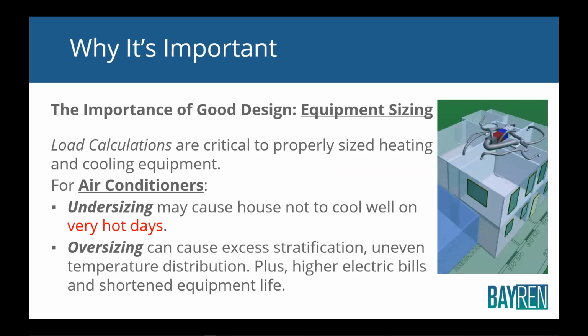The windows have more to do with the load of a house, and the direction they're facing, than the square footage of a house. So to size an air conditioner based on the square footage of the house is actually kind of dumb. I would be much more respectful of a contractor who says, I do so many tons per square foot of glass, or I look at west facing glass, that's how I size air conditioners. I would have much more respect for that than sizing based on square footage. But even that is not accurate enough. You have to do a load calc on a house, okay?